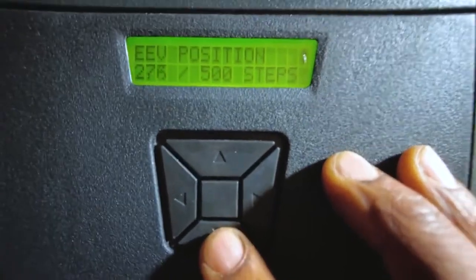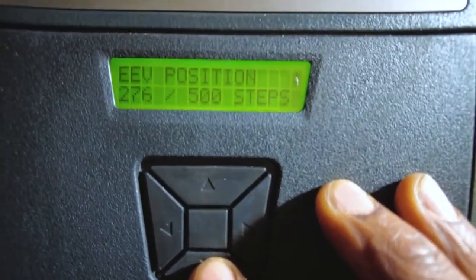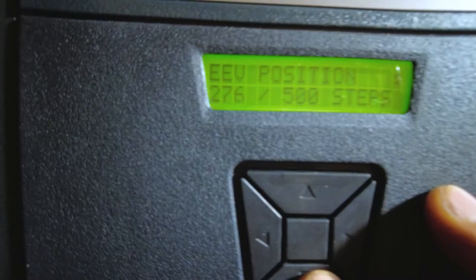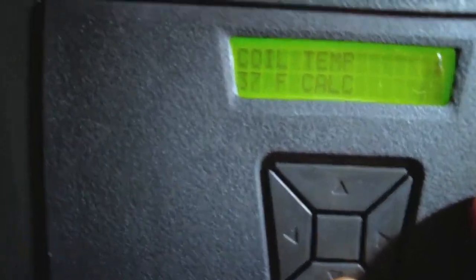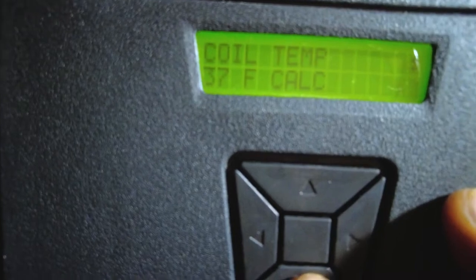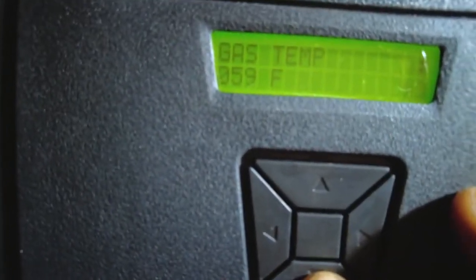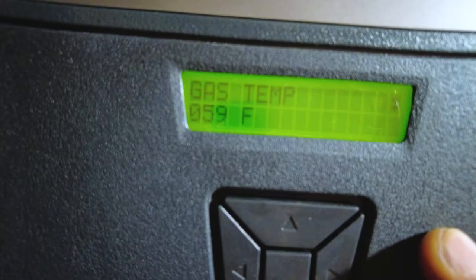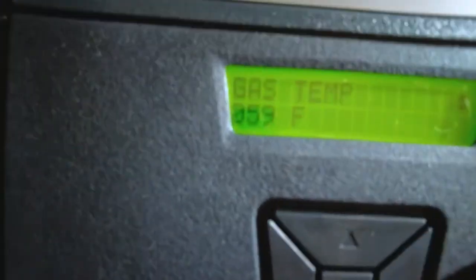Another thing I like about this monitor menu — as you can see now, the electronic expansion valve is a step down, it's about 50% open now, 276 steps. Coil temperature is 37 degrees right now. It's been running for about 5 minutes so far. Gas temperature 59. So now you can see before that was reading like 126. That's pretty much it.